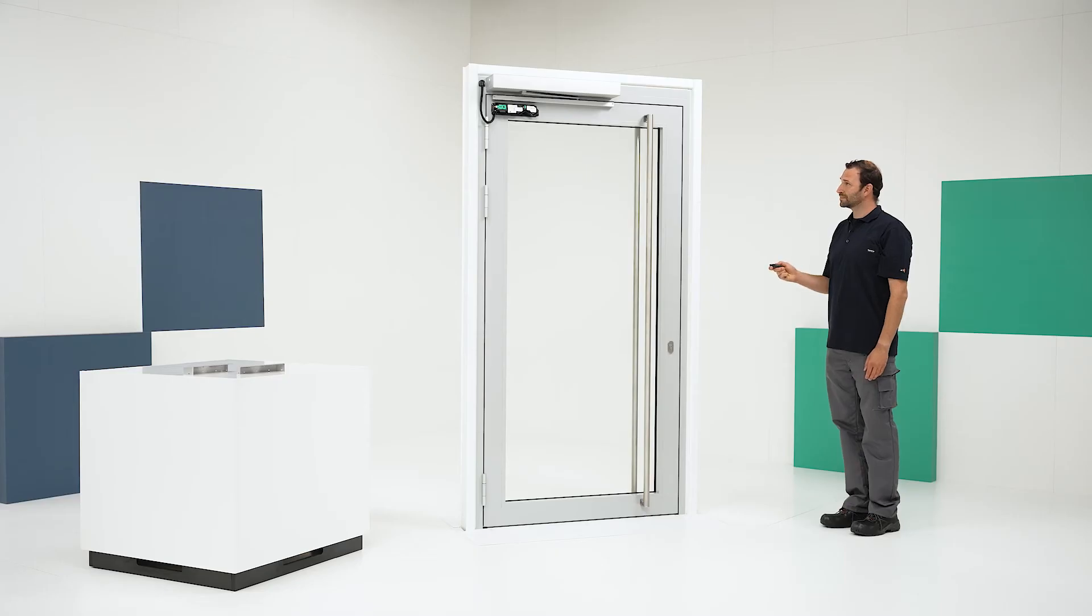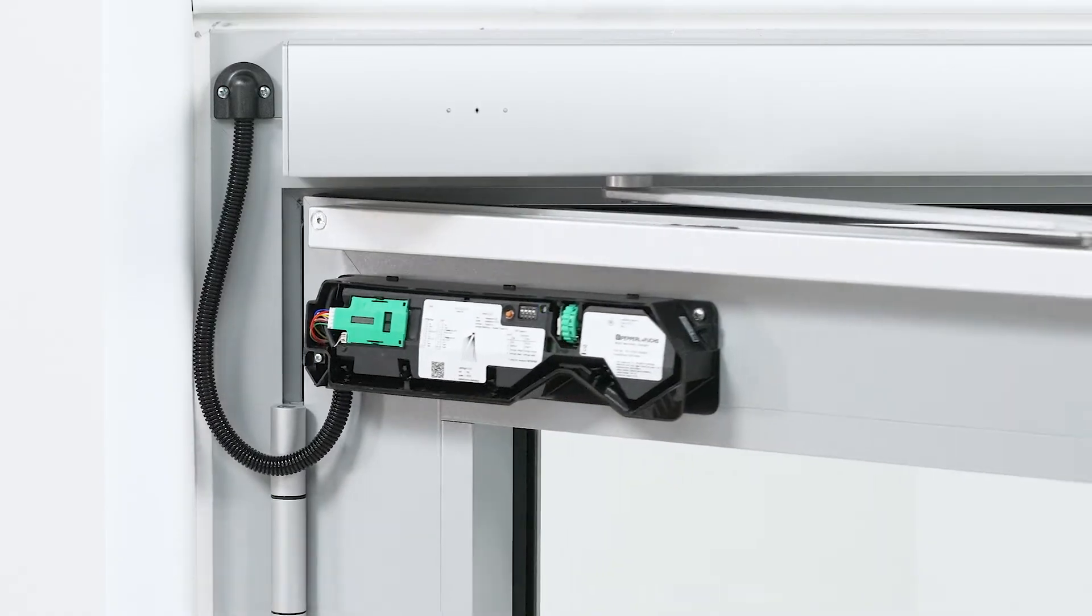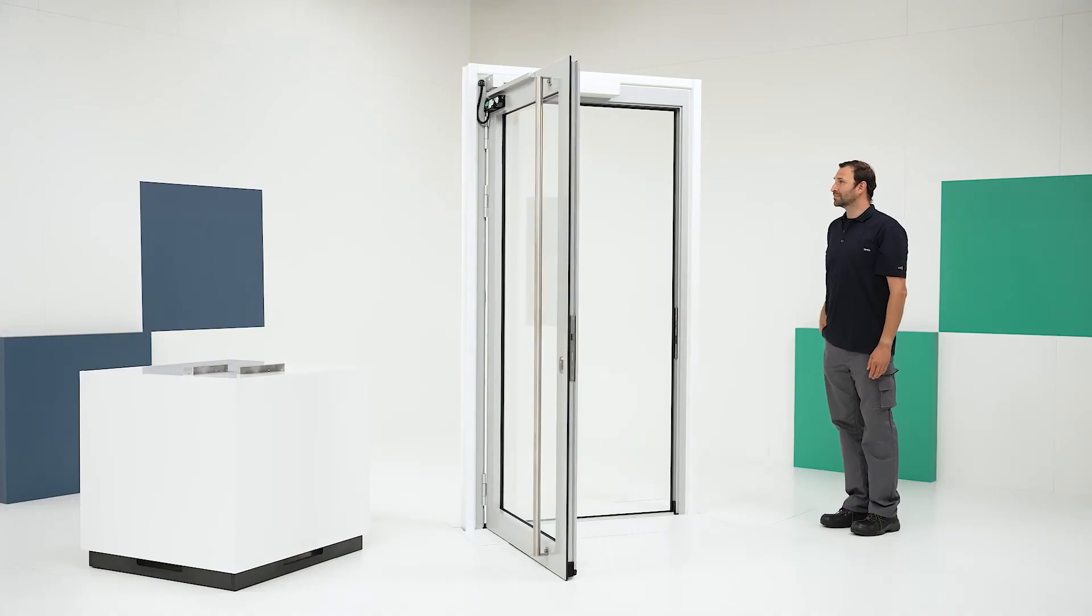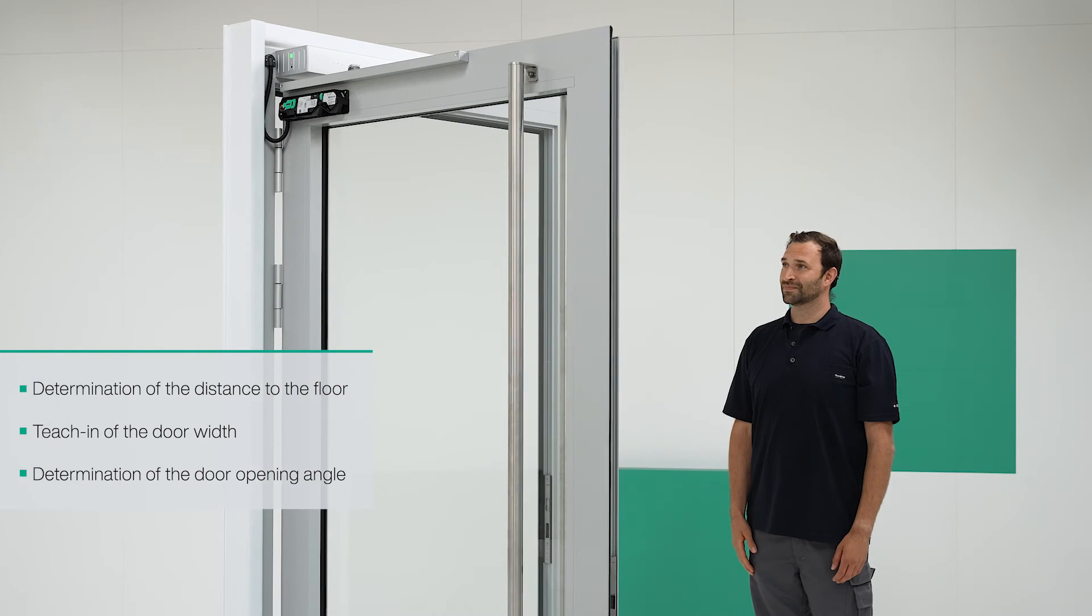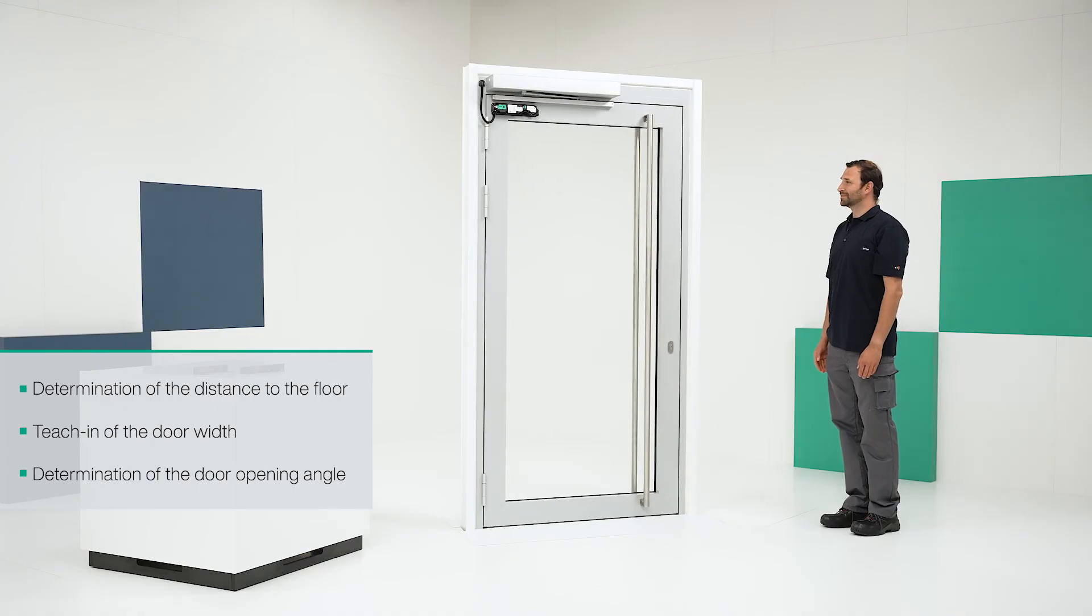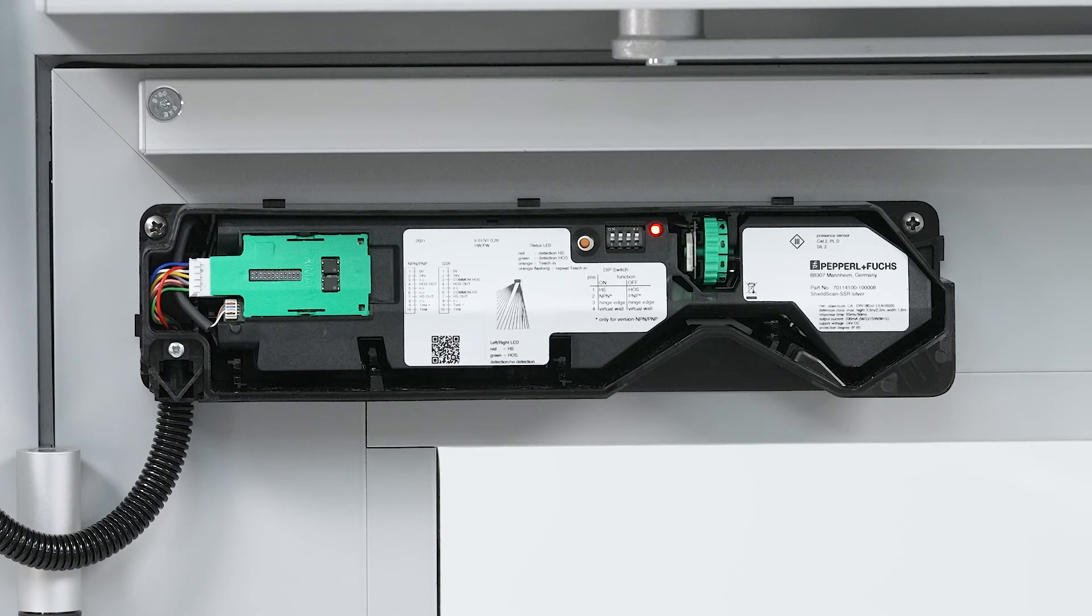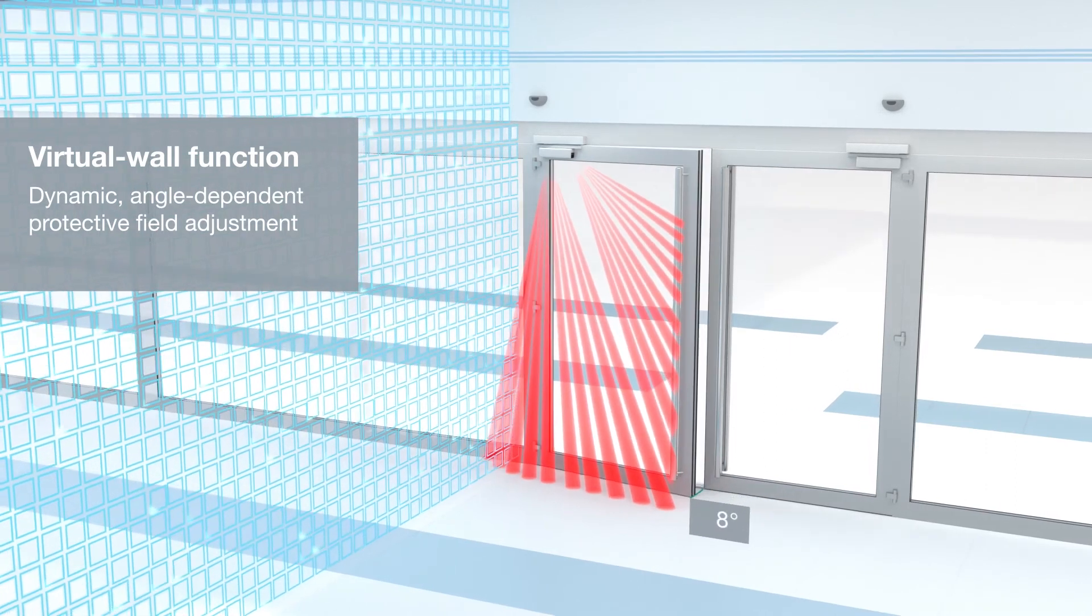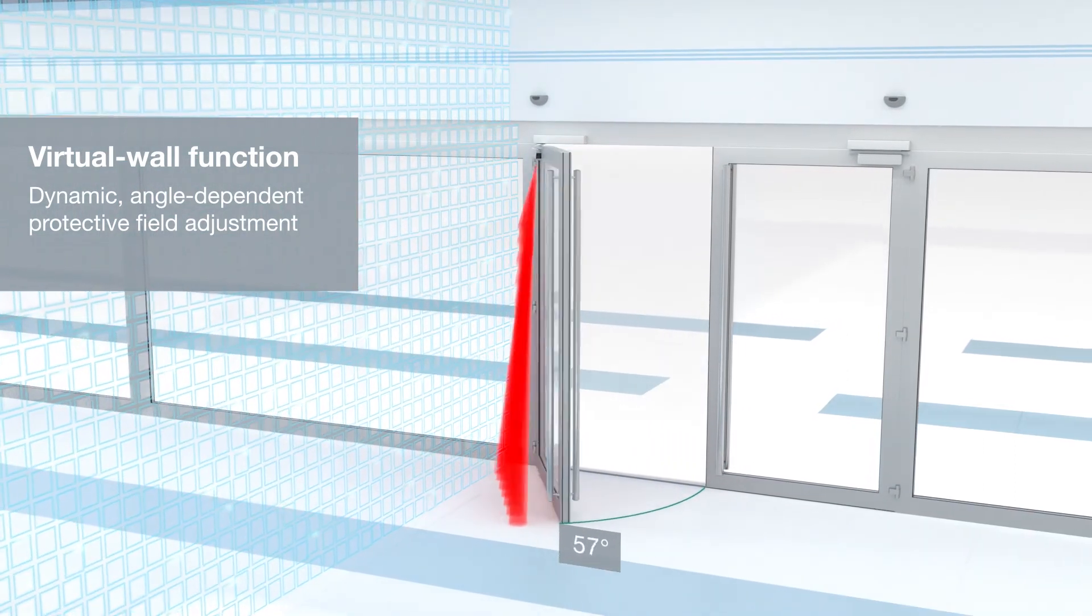Now it's time to start the door movement. The door opening angle is learned while the door is being opened. The status LED will flash green when this process is complete. As the door is closing, the status LED will flash red. When all the LEDs go out, this means the teach-in process has been completed successfully. The sensor system is now ready for operation and virtual wall suppression is activated.